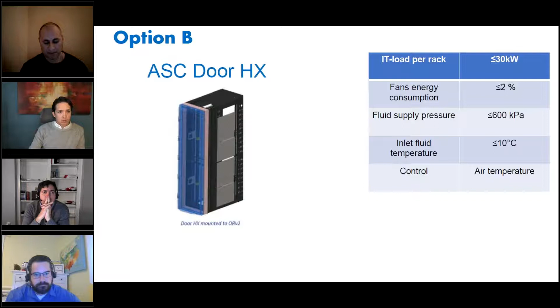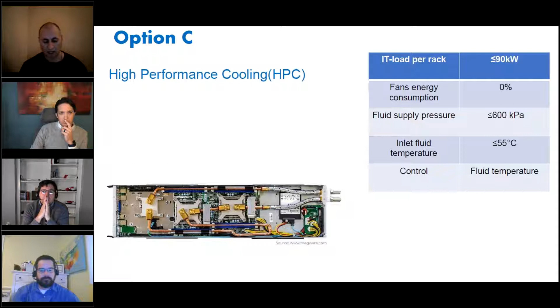With HPC, the capacity per rack grows up to 90 kilowatts, and we don't use fans for air circulation, but the technology is even more expensive than previous ones as there are many more connections. But we have an important advantage: the high temperature of cooling liquid, which means year-round free cooling and even waste heat usage in district heating.